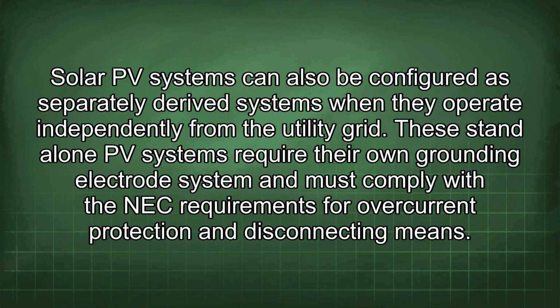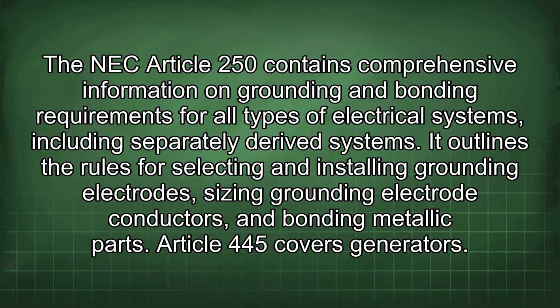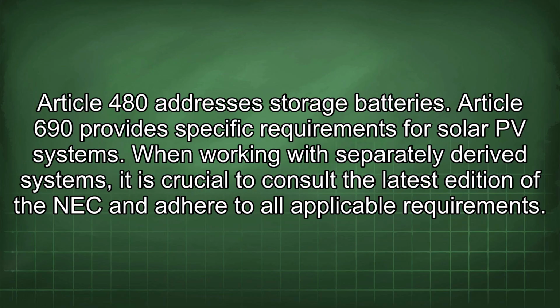These standalone PV systems require their own grounding electrode system and must comply with the NEC requirements for overcurrent protection and disconnecting means. The NEC Article 250 contains comprehensive information on grounding and bonding requirements for all types of electrical systems, including separately derived systems. It outlines the rules for selecting and installing grounding electrodes, sizing grounding electrode conductors, and bonding metallic parts. Article 445 covers generators. Article 480 addresses storage batteries.